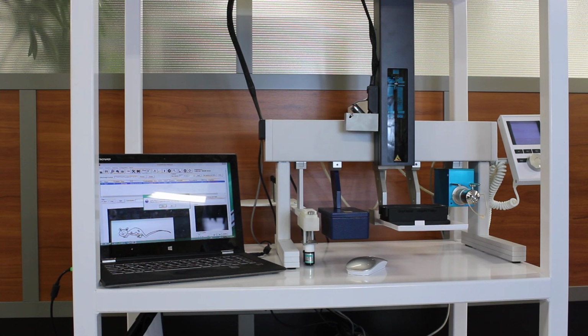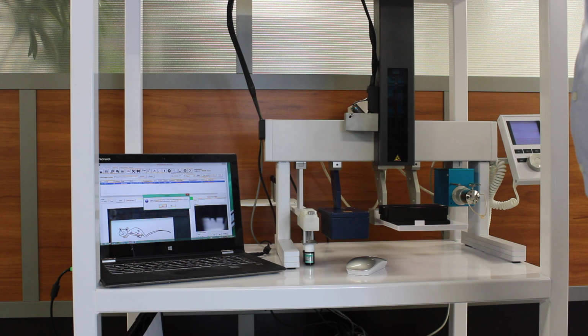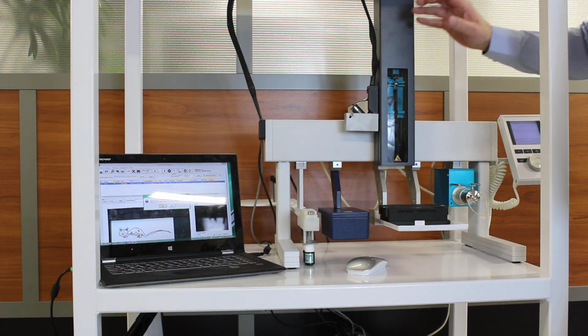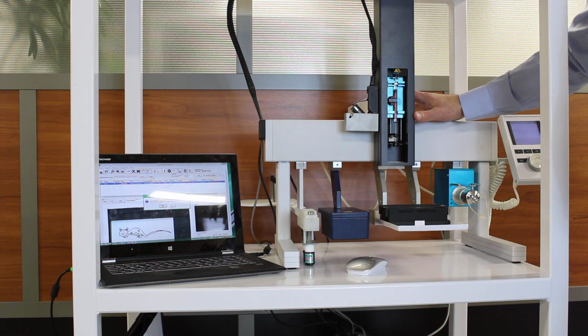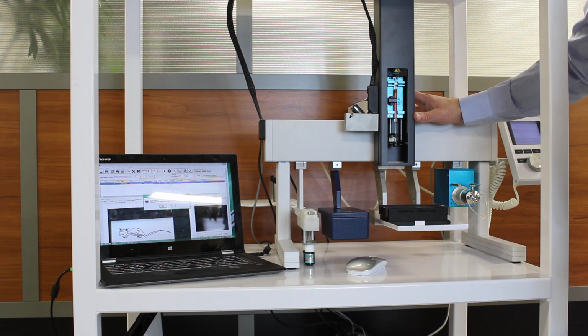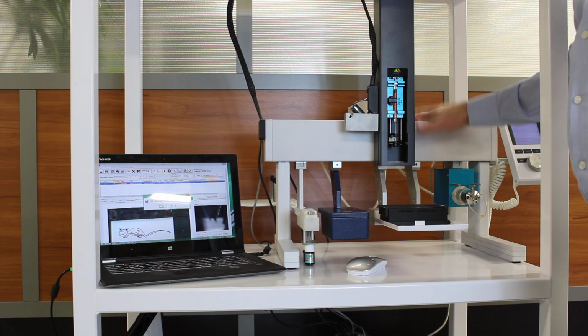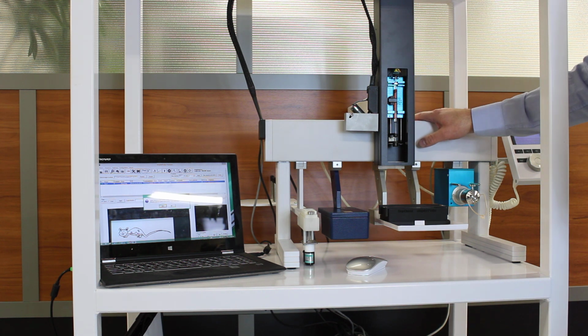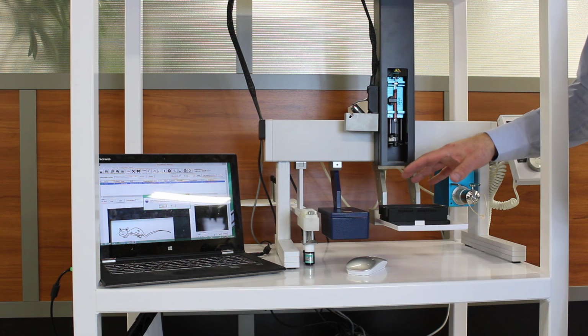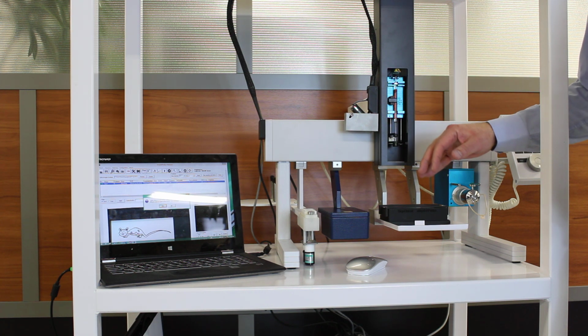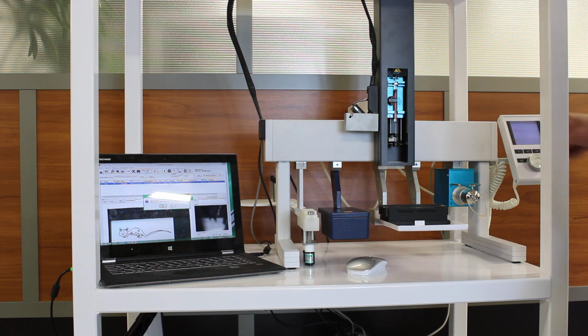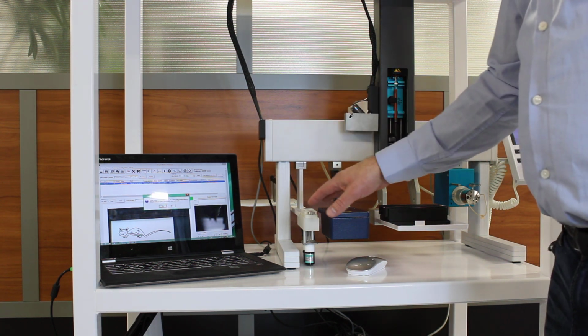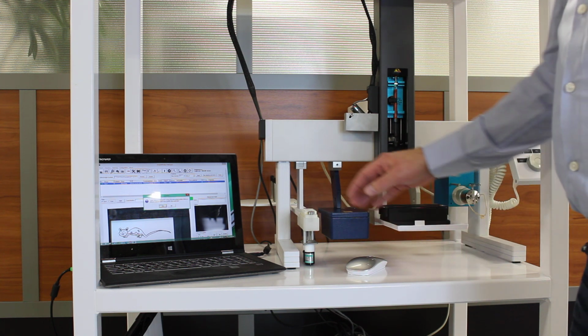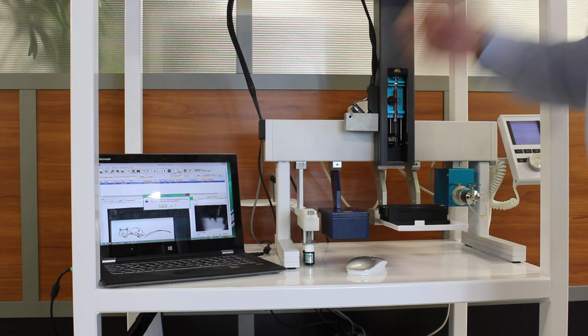Okay, I'd like to go over a little bit of the hardware here of the droplet probe system. Essentially, we got a standard XYZ robot manufactured by CTC Analytics. Very robust, flexible, open architecture. What we love about this system is it does what you need to do and then some. We can run as a standard LC, or in this case surface sampling as a droplet probe system. On the left side, we'll start with the wash station. We got 2 washes, 2 different solvents, and a waste.